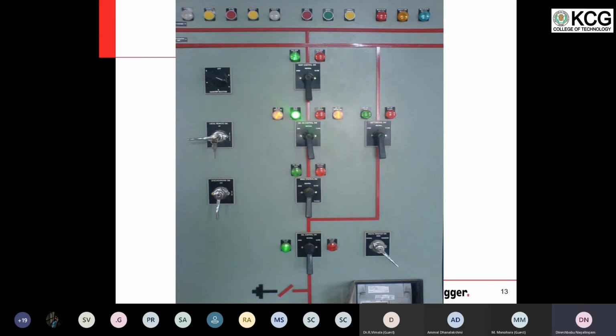Case two, another story. The isolator operating time is around 15 to 20 seconds. It's a slow mechanical movement and it will close. The breaker is a high-speed operation device. It operates in about 100 milliseconds. Even high-speed SF6 breakers will trip in 40 milliseconds. 25 to 40 milliseconds is the operating time in 400 kV or 765 kV breakers. So the second case or story that we told was the operation time of isolator and breaker.